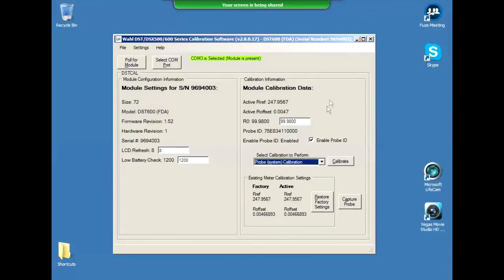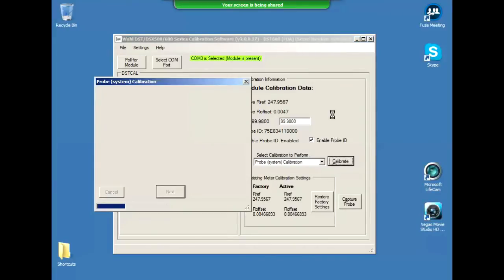And what I'm going to do, we've selected probe system calibration from our drop-down menu here, and we're going to hit the calibrate button, and it's going to pop up a window that will tell us to put the probe in an ice bath if we haven't already done that. We've actually already done that, and it's a good idea to let it stabilize. We're pretty close there. So I'm going to hit next.